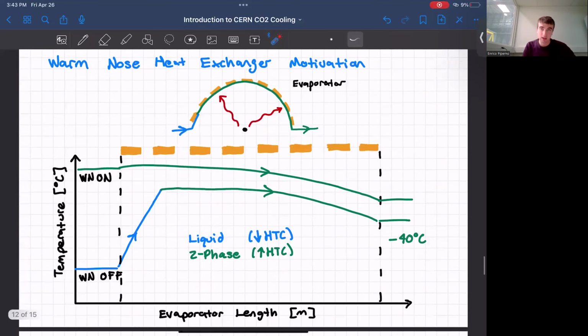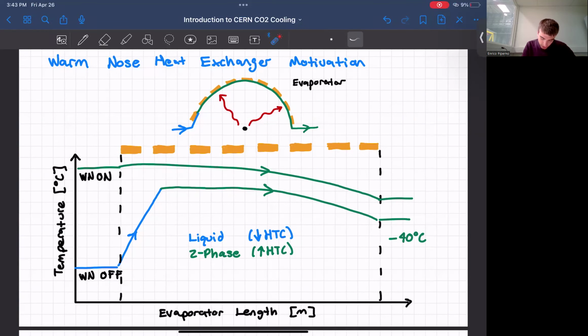On this slide, I will describe why the warm nose is implemented. With the warm nose off, if the geometry is not calibrated properly, the refrigerant will enter the evaporator in liquid, and then right after the heating, it will increase in temperature and then boil. However, the warm nose increases enthalpy before the capillary, and as a result, the refrigerant enters already boiling, or already in two-phase. Therefore, the temperature across the evaporators is much more consistent compared to the warm nose off.